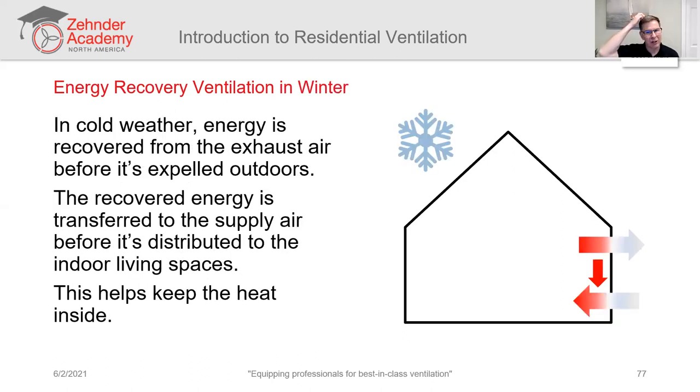So again, we'll start in a cold climate, heating season in winter. The indoor air is warmer. And so as you run your exhaust air and your supply air through the same appliance, an ERV or an HRV, you're going to extract heat from your exhaust air and deliver that to the incoming supply air. So you're transferring energy. We'll see briefly in a moment that this is done passively, not actively, typically. But nonetheless, you're recovering energy from the indoor air before you pump it outside as exhaust air.